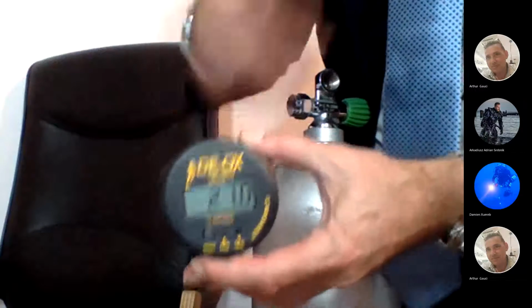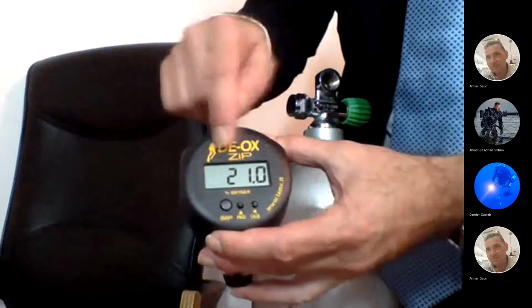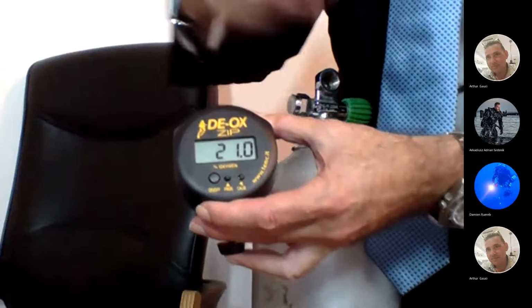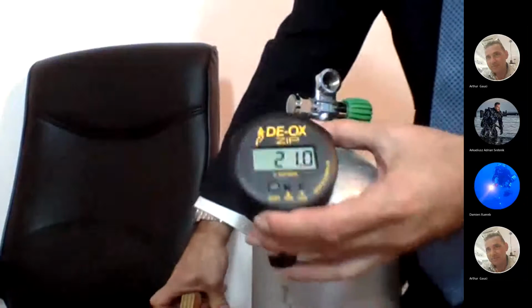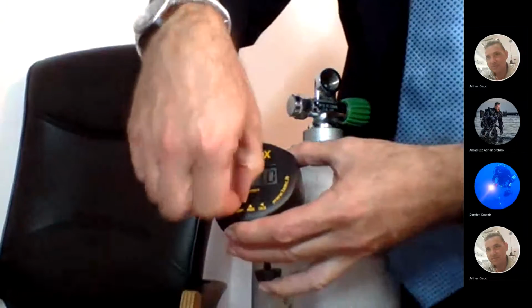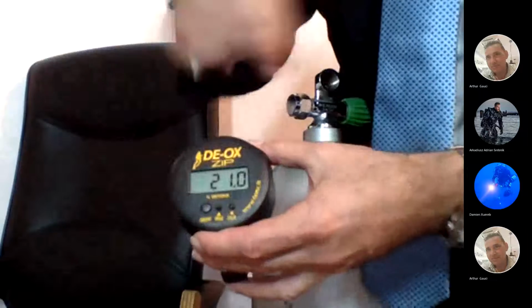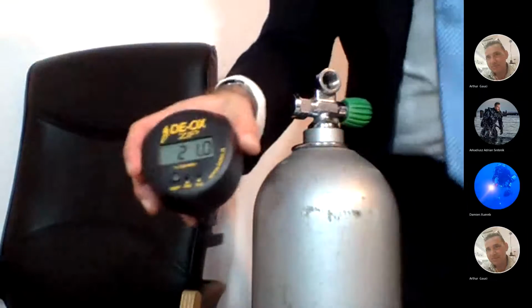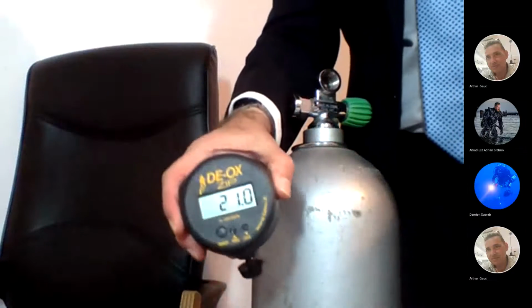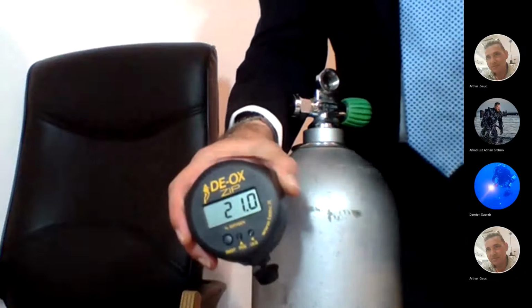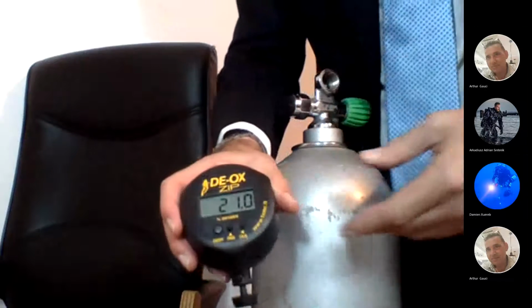Unfortunately I gave you a very high quality sensor and analyzer, but generally you don't go up to 21 - it stays at 21.3, 21.5, 21.9. And what do people do? They force the calibration, the manual calibration, and go back to 21. Then you totally spoil the analyzer, and it becomes very difficult to get back to the real analysis.